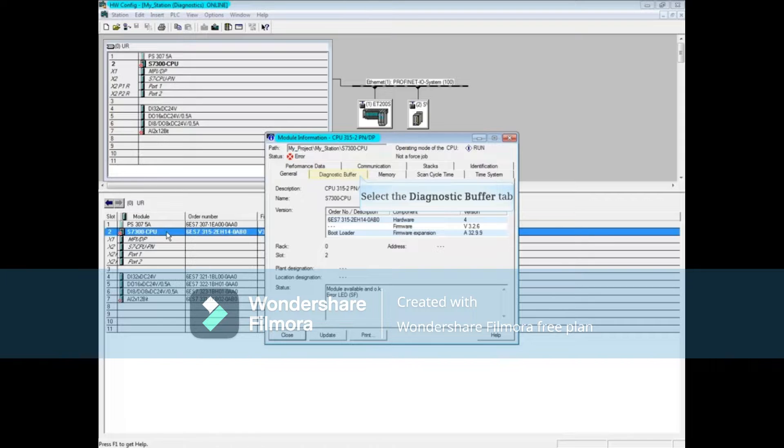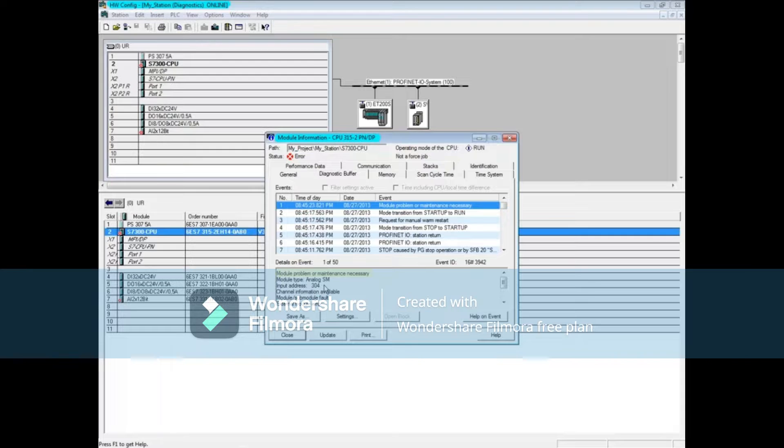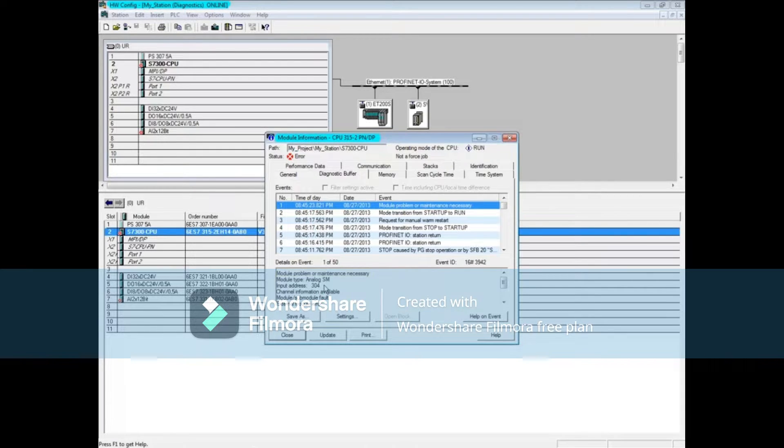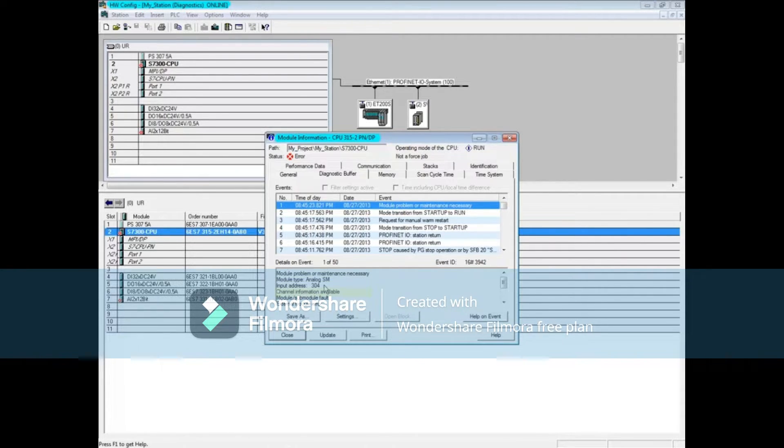Click the Diagnostic Buffer tab. Message 1 indicates that there's a problem with or maintenance is needed for a module. The module type is an analog signal module with the input address 304.